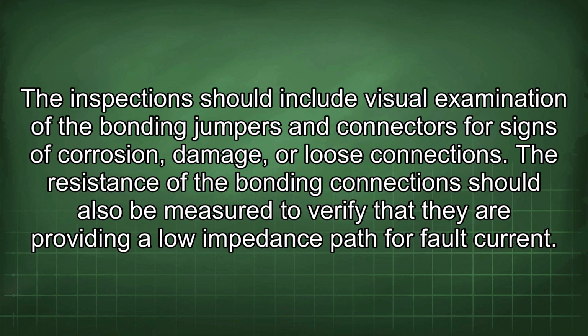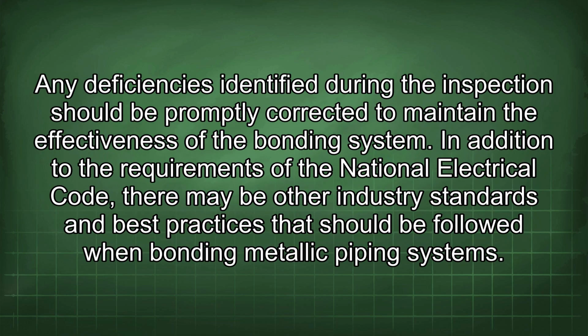The resistance of the bonding connections should also be measured to verify that they are providing a low impedance path for fault current. Any deficiencies identified during the inspection should be promptly corrected to maintain the effectiveness of the bonding system. In addition to the requirements of the National Electrical Code, there may be other industry standards and best practices that should be followed when bonding metallic piping systems.